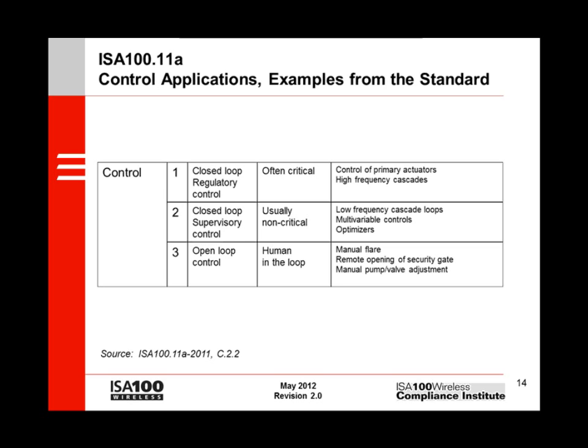Moving up to control class 2, we have closed-loop supervisory controls. These are usually non-critical. Examples include low-frequency cascade loops, multivariable controls, and optimizers. At the top of the ISA100.11a control hierarchy, we have control class 1. The standard describes direct control of primary actuators, such as where a host connection is available on demand 99.99% of the time or more, with link outages of more than a half-second intolerable, and with demand rates once every four seconds. High-frequency cascades are also mentioned.